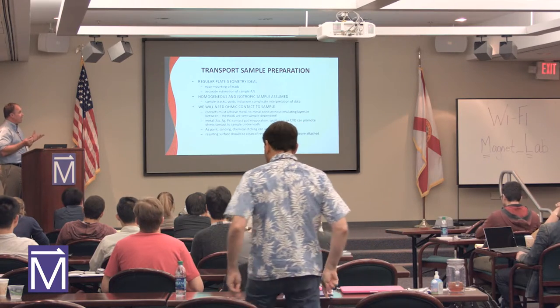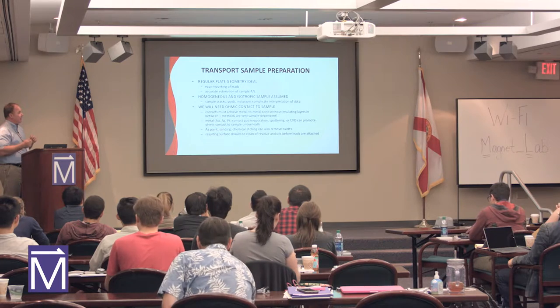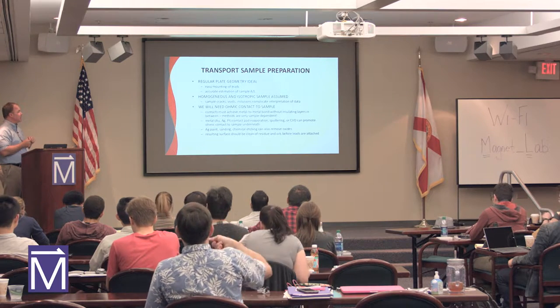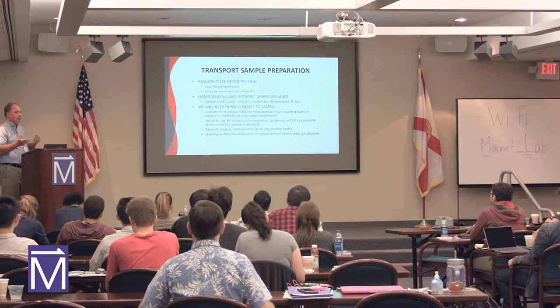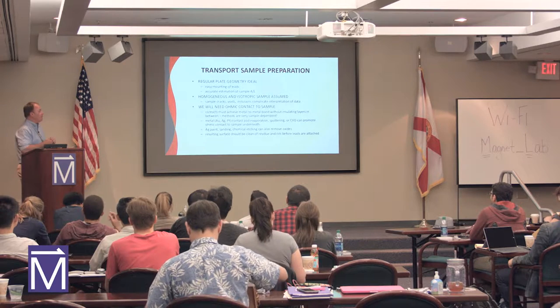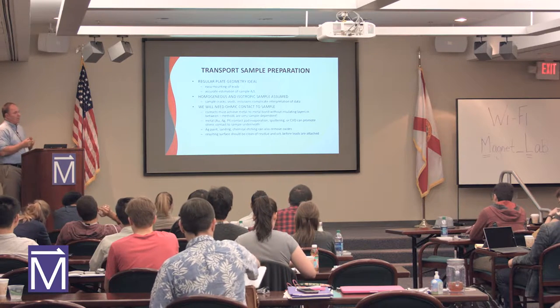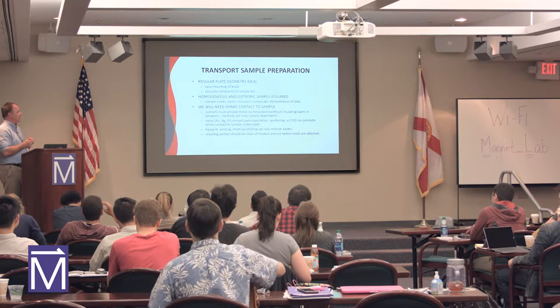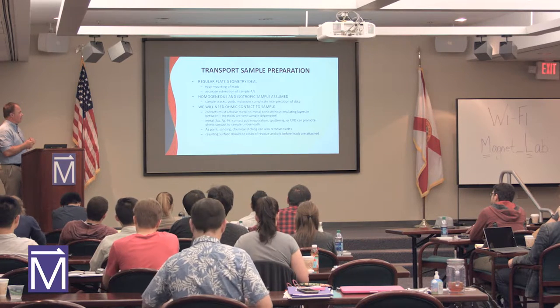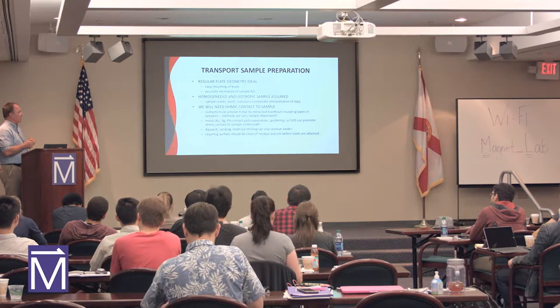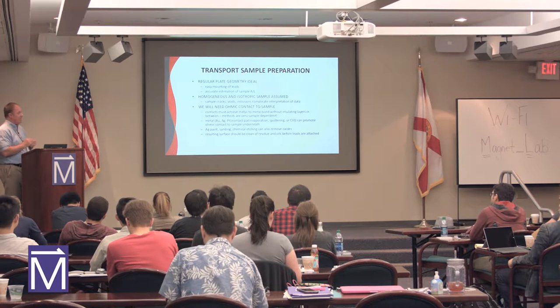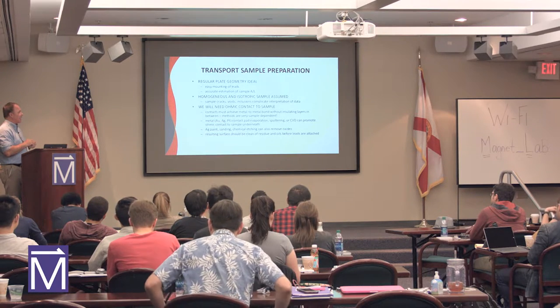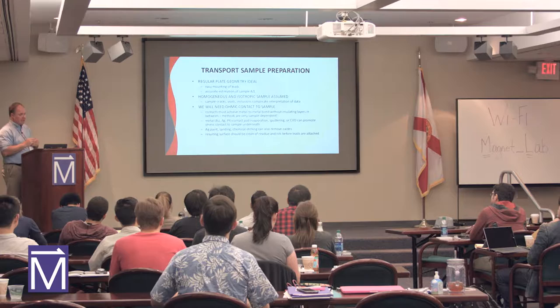How do we prepare the sample? You typically want a plate geometry to put the sample. It's typically what you have. You can measure the dimensions of the sample, the length and the area and the thickness. You want to have a homogeneous sample if you can. Don't have it cracked or any voids in the sample.